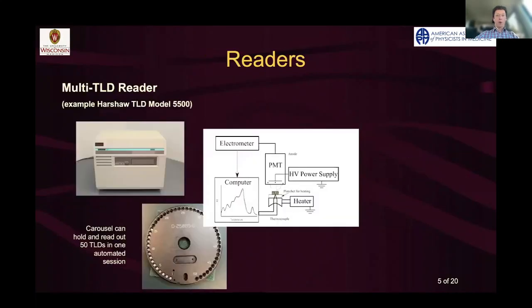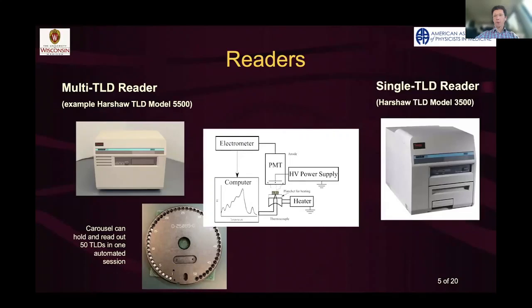The readers, there are a variety of readers on the market. This is a common one if you have a pretty big TLD program that you operate. It's called a Model 5500 from Harshaw. It has a carousel that rotates around and it can hold up to 50 TLDs and read out all of them in one automated session by heating them with nitrogen gas, lifting them up in the air, and the light is recorded on a photomultiplier tube. It's a very nice system. It's very efficient.